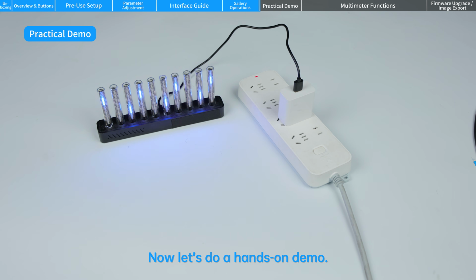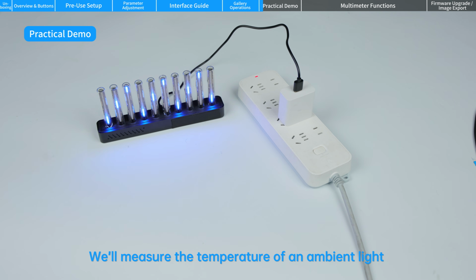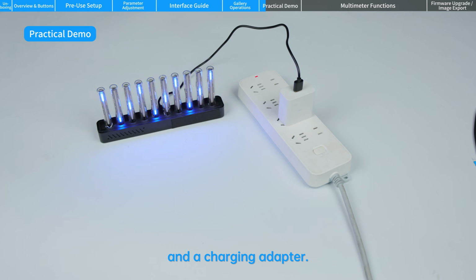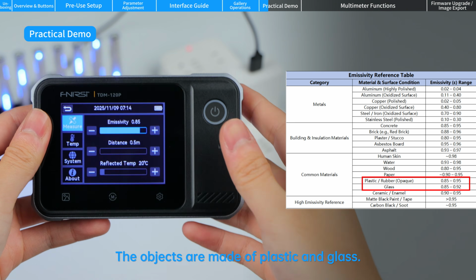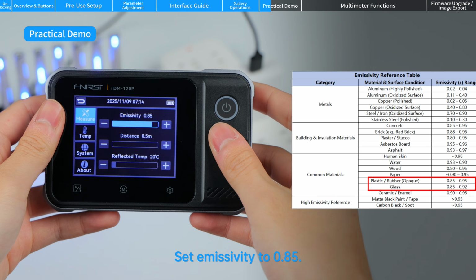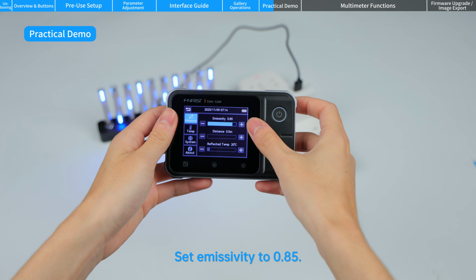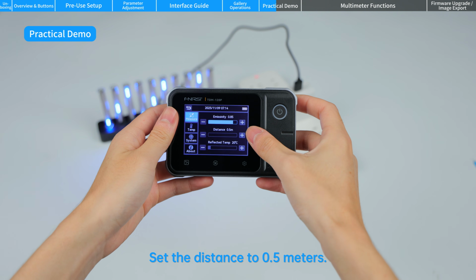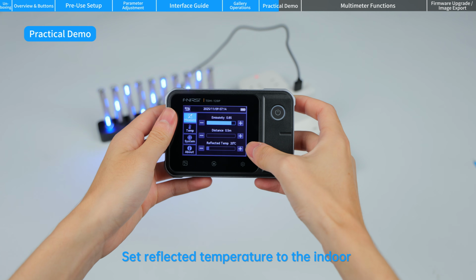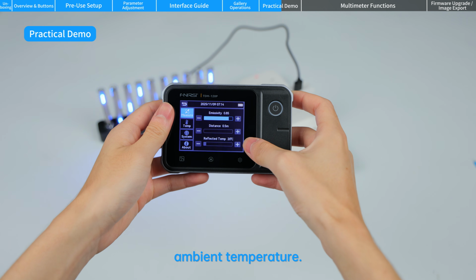Now let's do a hands-on demo. We'll measure the temperature of an ambient light and a charging adapter. The objects are made of plastic and glass. Set emissivity to 0.85. Set the distance to 0.5 meters. Set reflected temperature to the indoor ambient temperature.